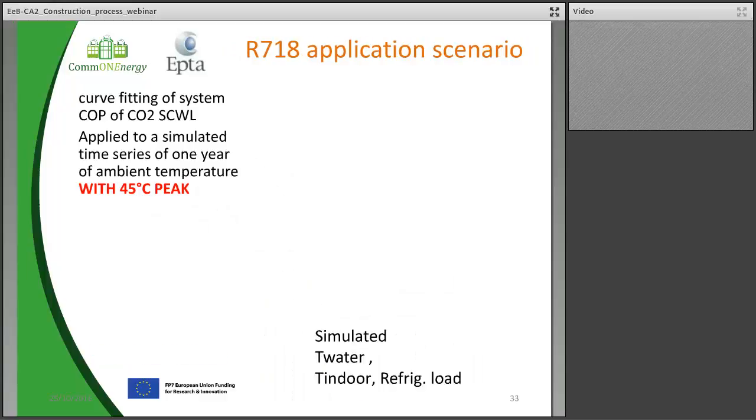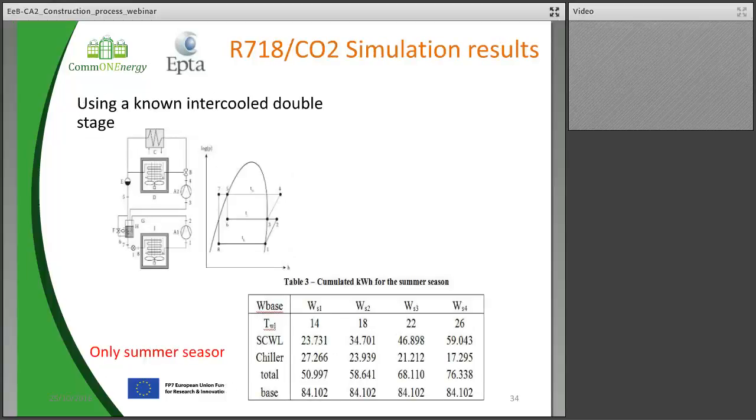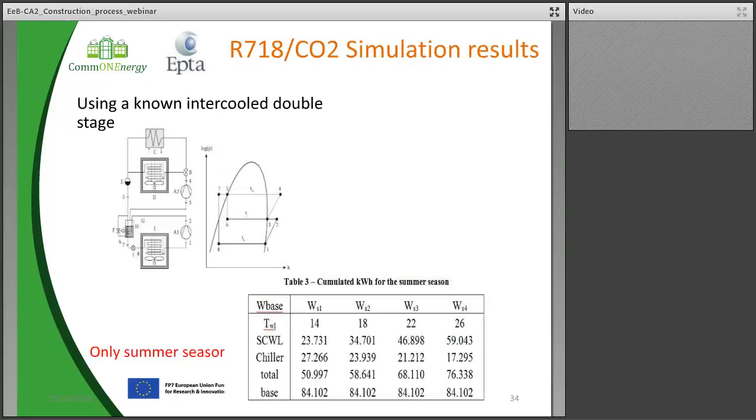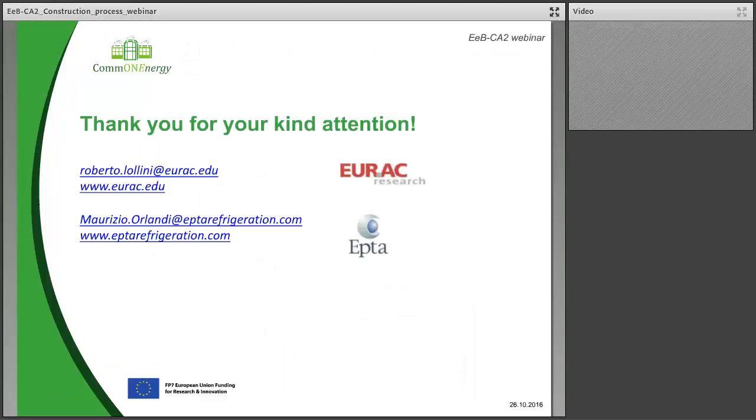Sorry again, I'm missing diagrams, but I have to tell you what the content was. In this we tried an application scenario, and water as a refrigerant can be very good, even better than ammonia and propane, when small temperature differences are considered. So the very good application thought for our case is, why not add this kind of machine to cool the water of a CO2 system.